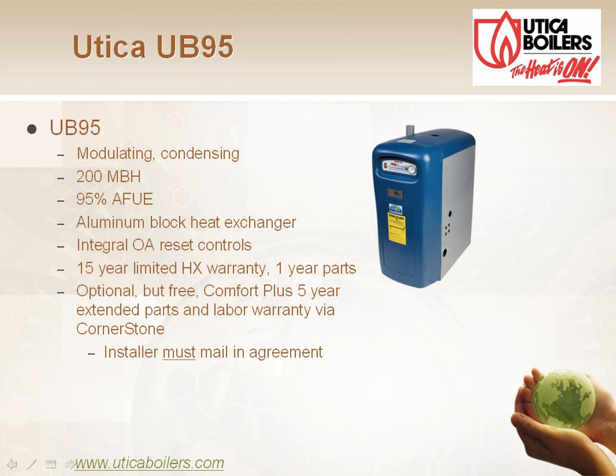This Utica UB95 is designed to directly replace the cast iron boiler without having to change the piping arrangement. So if I don't have primary secondary today, I take out an old cast iron boiler, I put this guy in, I don't have to change the piping, right? There's still benefits to doing primary and secondary piping, but the boiler's not going to make me do that, right? The application might, but the boiler's not going to.